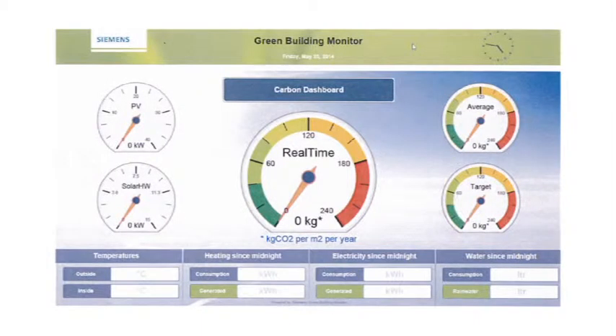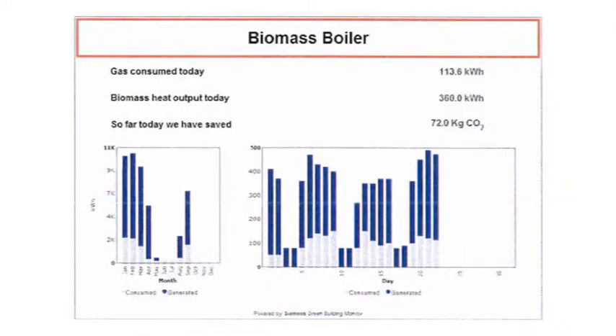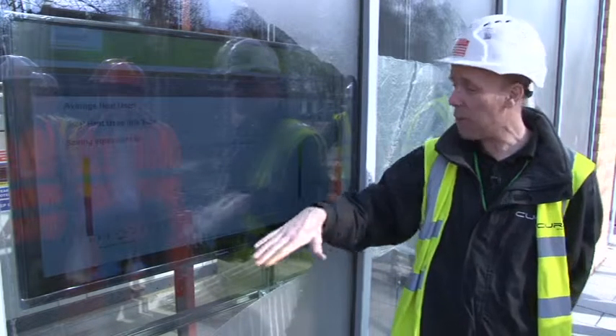First screen is the consumption for the building. This showed electricity, gas and water. Second screen is the heating provided by the CHP unit. What it will give you is the consumed amount of heat and the generated amount of heat. Until the system is fully running and the building's occupied, these values will change dramatically, and then you'll get a nice graph of we've produced 60 kilowatts of heating and we used 60 kilowatts of heating.